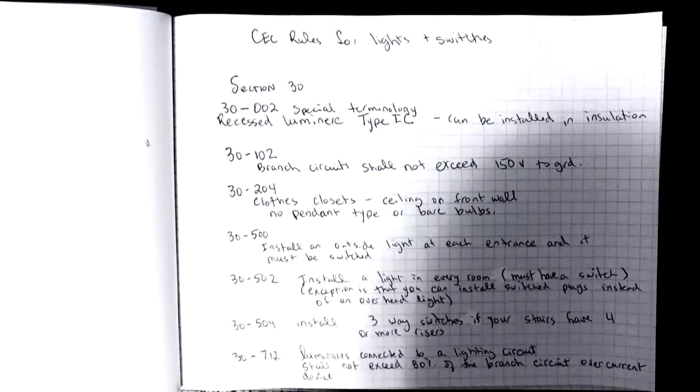30-502 indicates that we need to install a light in every room and it must have a switch. The exception to that is in a master bedroom or bedroom where you have switched plugs, then you don't have to have an overhead light.